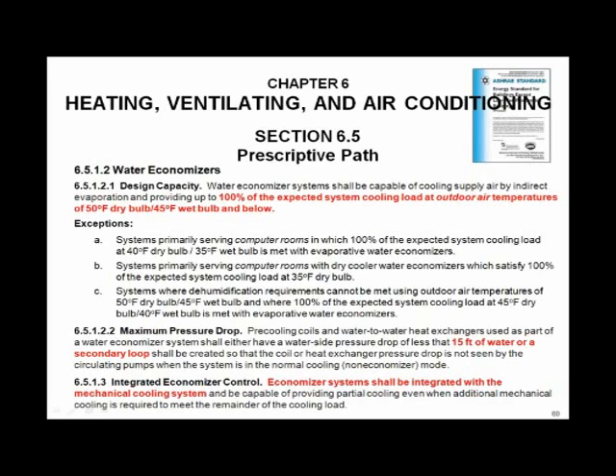The other thing I think that's really new, that's really catching people off guard, is the last statement at the bottom of this page, 6.5.1.3. Integrated economizer control. The economizer system shall be integrated with the mechanical cooling. And keep reading it so that you can have partial economizer running at the same time that the mechanical cooling is running. In other words, you want to be able to run both at the same time.